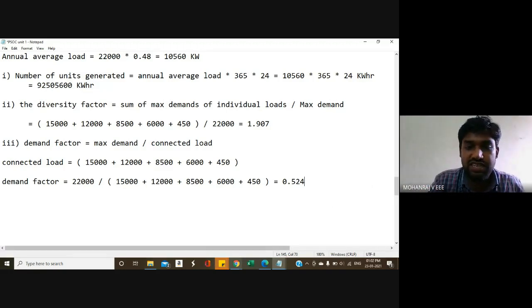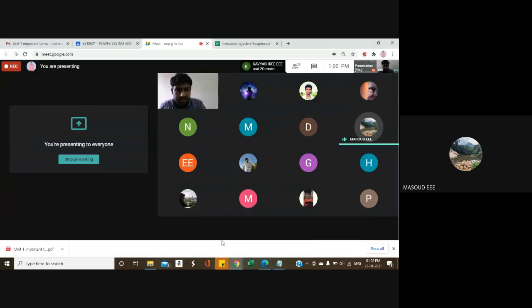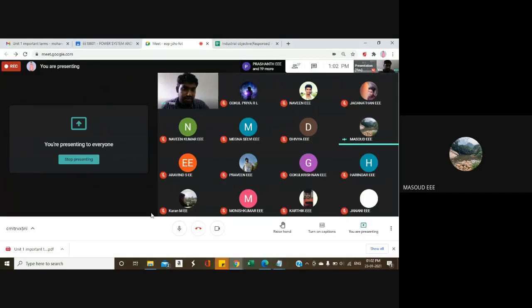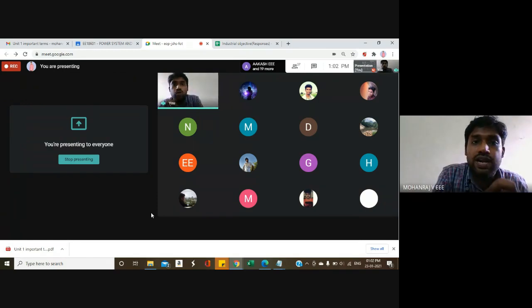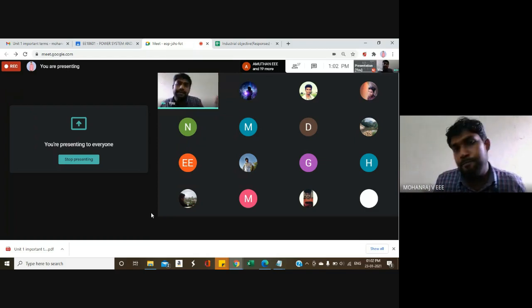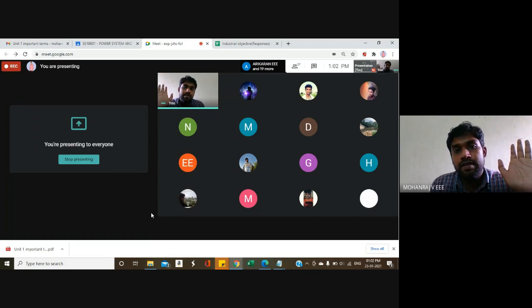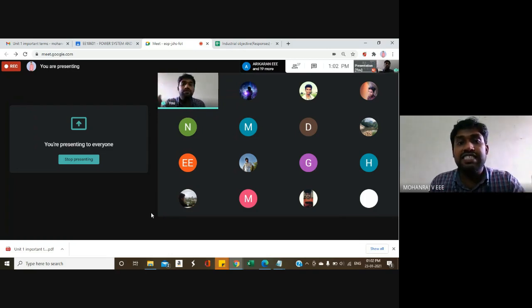Did I answer your question, Masood? Yes, sir. You may ask why I took the value of load 1 as its maximum demand. Because in this question, they have not given the maximum demand for load 1, load 2, load 3, load 4, load 5 explicitly, I took each load by itself as its maximum demand.